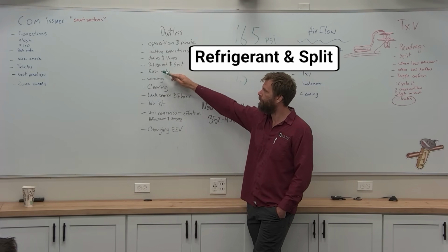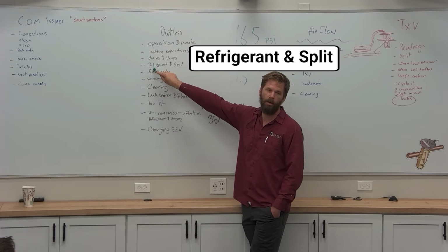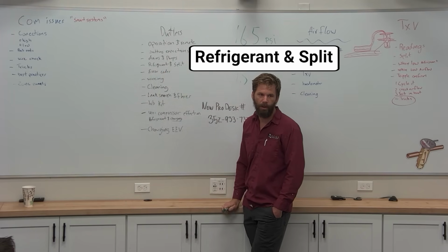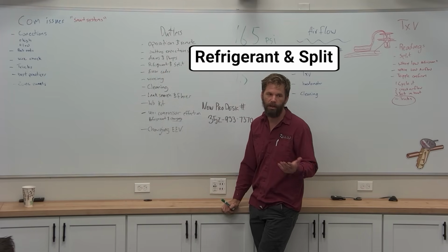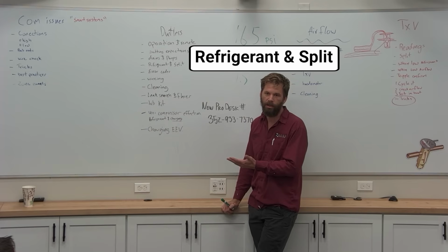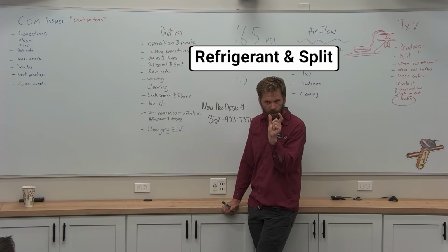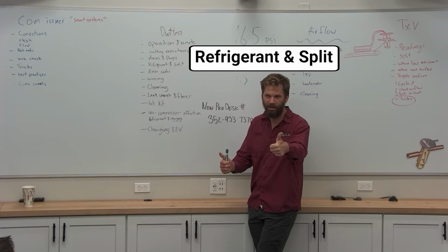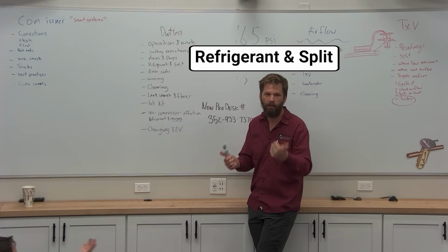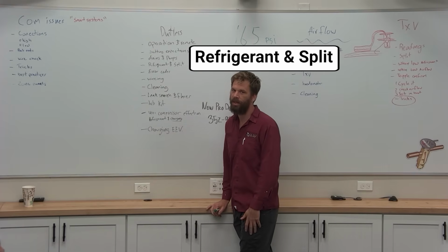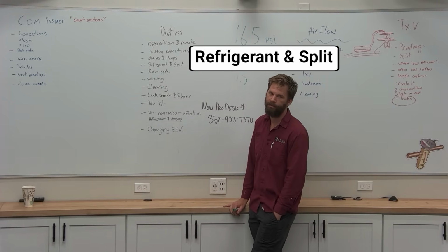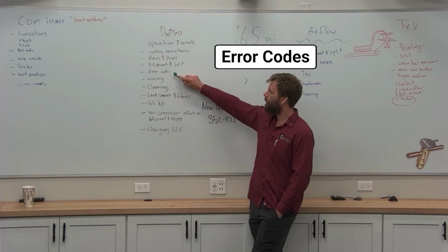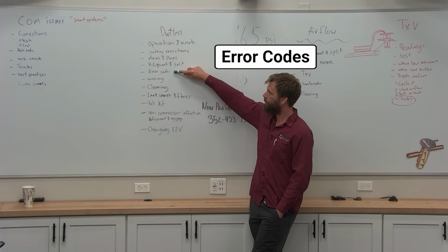Refrigerant and split. It's lower than you think, but if it doesn't have a low superheat, then it's probably low on refrigerant. You could be 109 psi, 32 saturation, and 2 degrees of superheat. Great. It's gorgeous. This thing is running perfect. It's not low. High superheat? Yeah, we are low on refrigerant. Error codes, manuals, tech support.